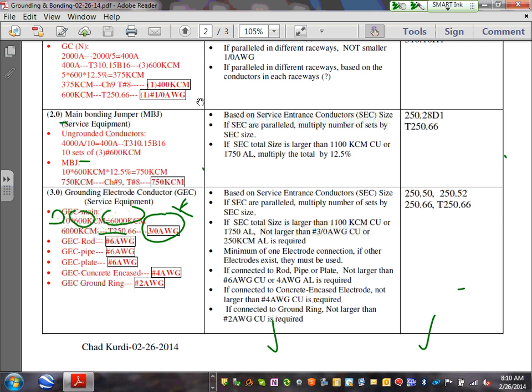No need to go larger than 3 aught. Now, the grounding electrode conductor going to the rod does not have to be more than number 6. To the pipe, not more than number 6. To the plate, not more than number 6. To the concrete-encased electrode, not more than number 4. And to the ground ring, not more than number 2. You can see that? These are always typical, not more. Now, can you put them bigger than that? Bring it on, but not more than that.